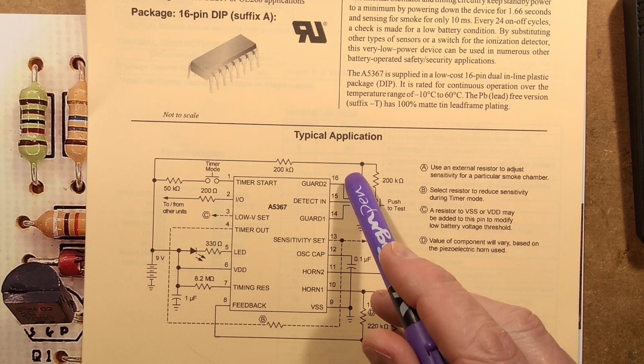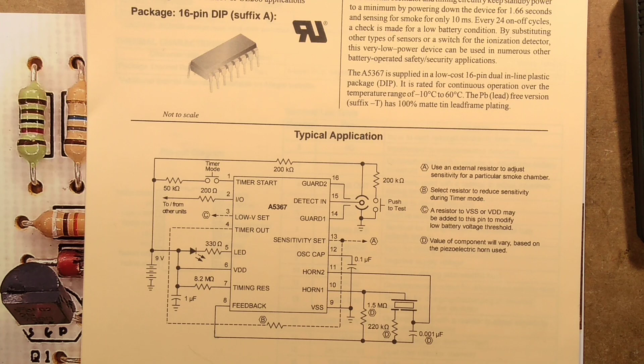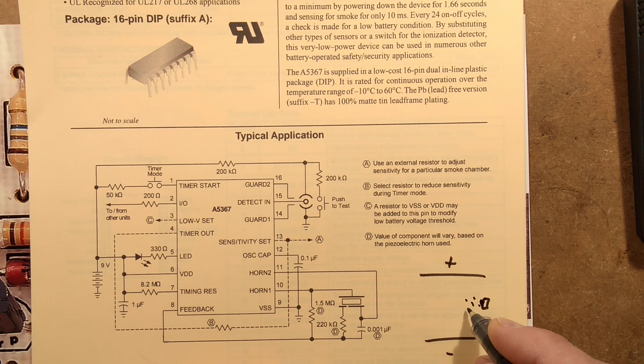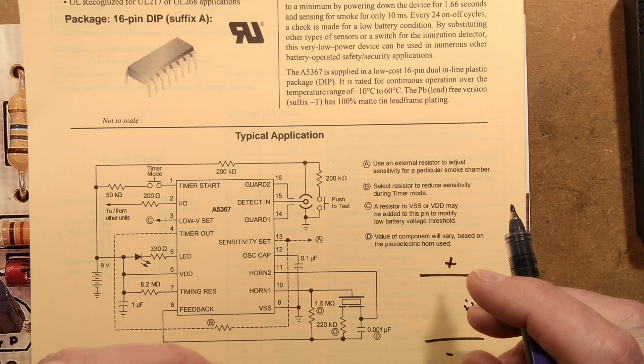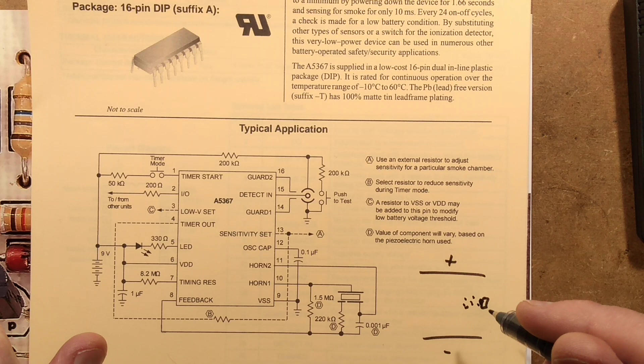Interesting things worth mentioning: the circuitry has compensating circuitry around the detector, because an ionization detector works in quite an unusual way. It has a positive plate and a negative plate, and a little emitter of americium, which emits radiation and ionizes the air inside, making it conductive so it acts like a resistor. The more smoke and pollutant in the air, the more it blocks the transfer of charge across - as far as I can see, its resistance rises with the level of smoke and contaminants in the air, which is interesting.